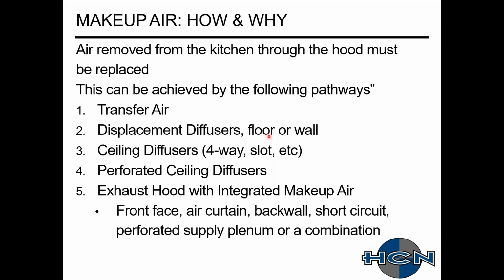The problem with using displacement diffusers, floor or wall is that kitchen spaces are notoriously busy, and that space is very valuable to those guys with their cooking equipment, so you can't just throw diffusers all over the place. Ceiling diffusers, 4-ways, slots, your perforated ceiling diffusers, and then the exhaust hoods with your integrated approaches. You'll have air curtains, front face, your back wall or back return, short circuit or internal comp, your perforated supply plenums, or any kind of combination with these and the other above mentioned.